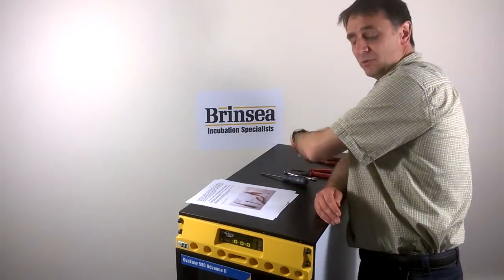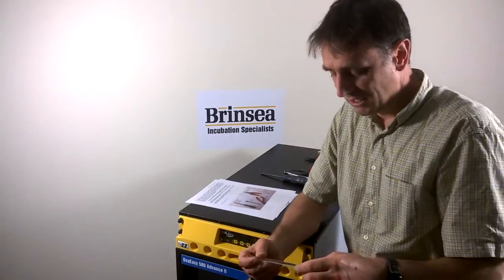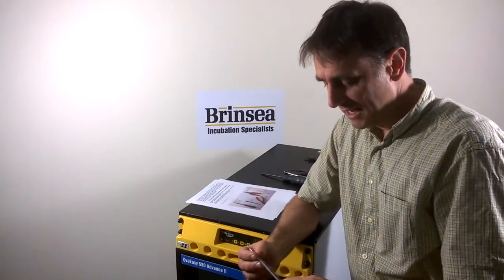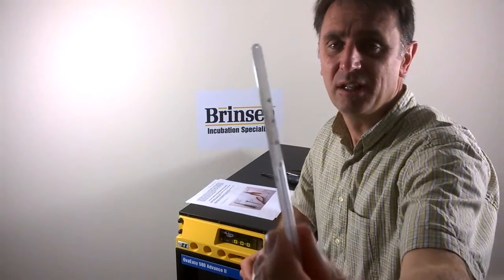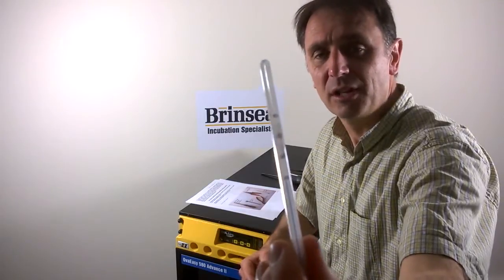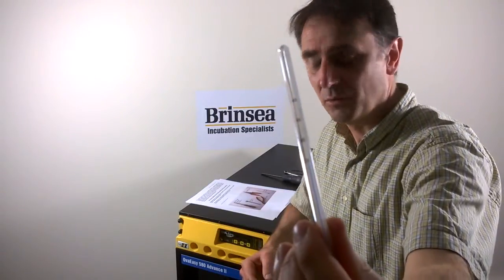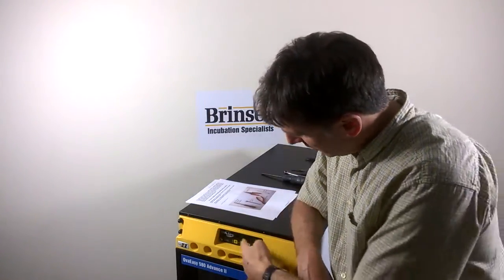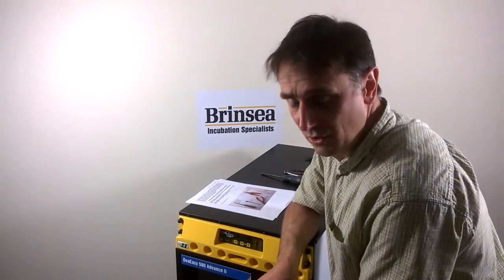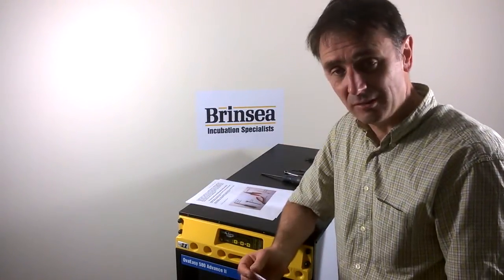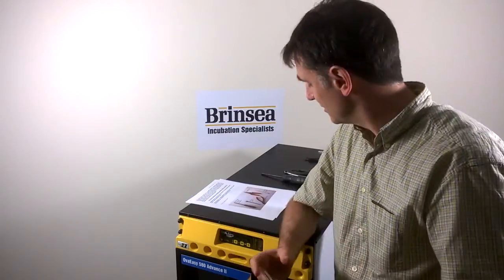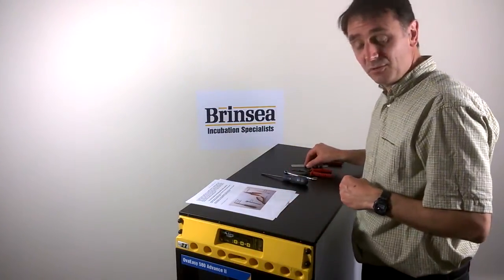And afterwards, once you've put the replacement unit in, you'll need a calibration thermometer like this one, so that you can calibrate your machine and make sure that what it's saying on the menu is what you've actually got in terms of temperature in the machine. We'll demonstrate how you do this. So those are the tools that you need.